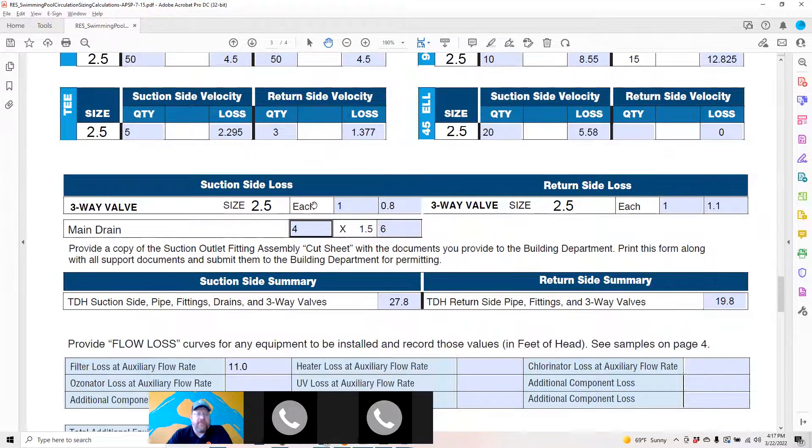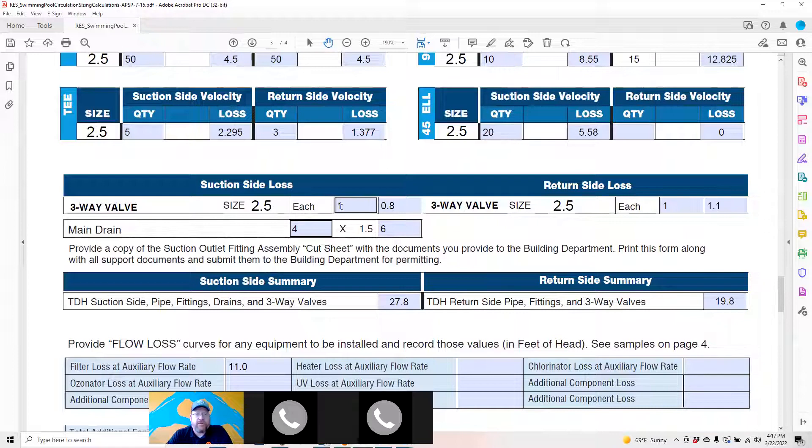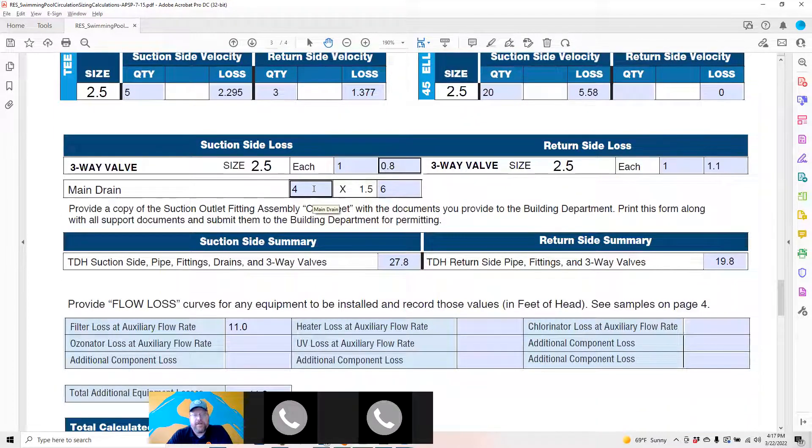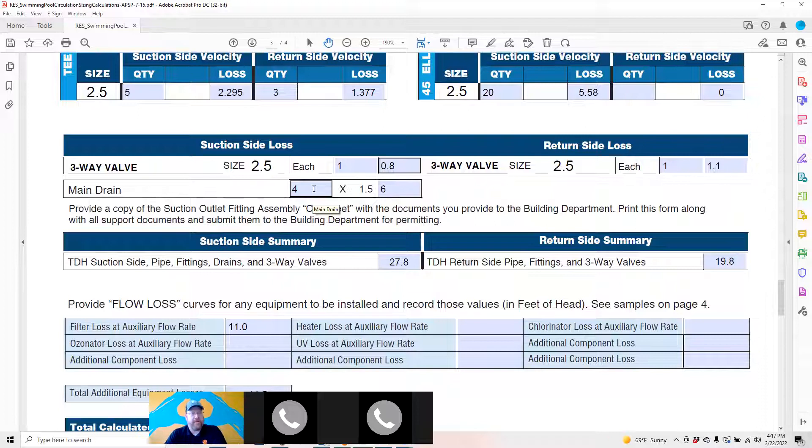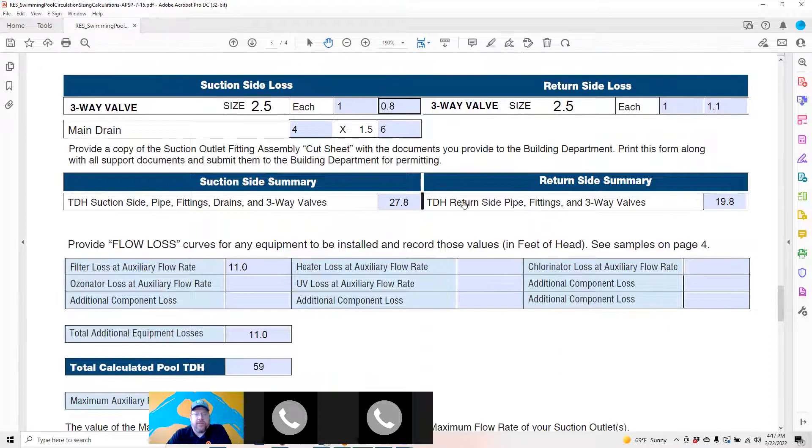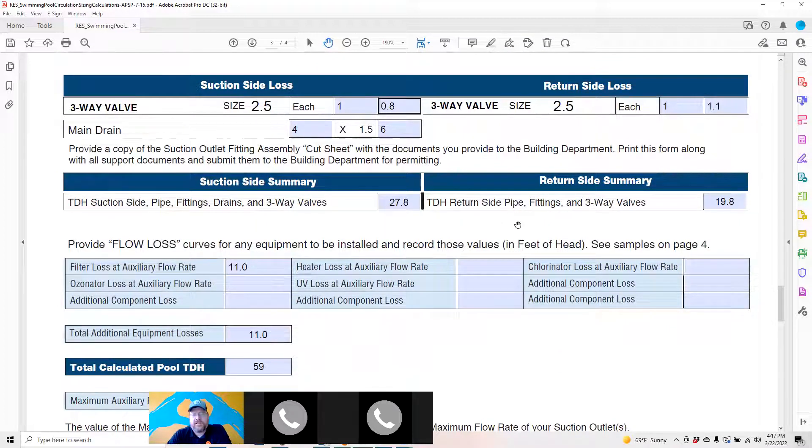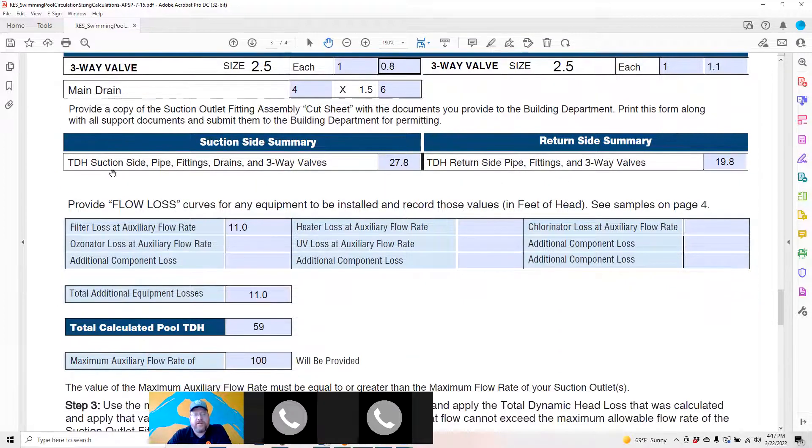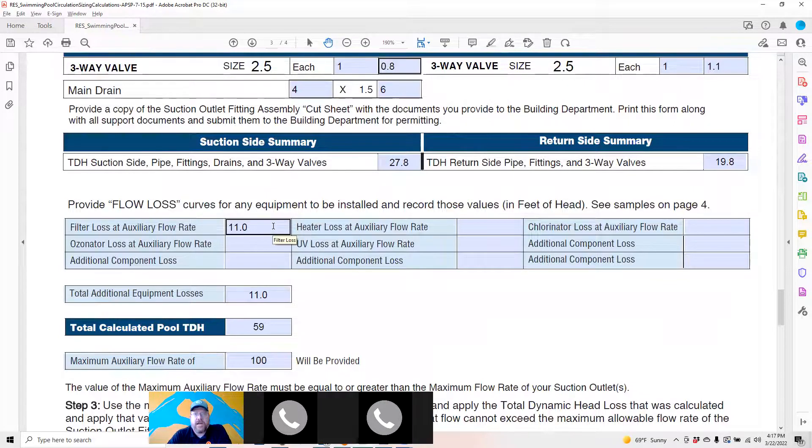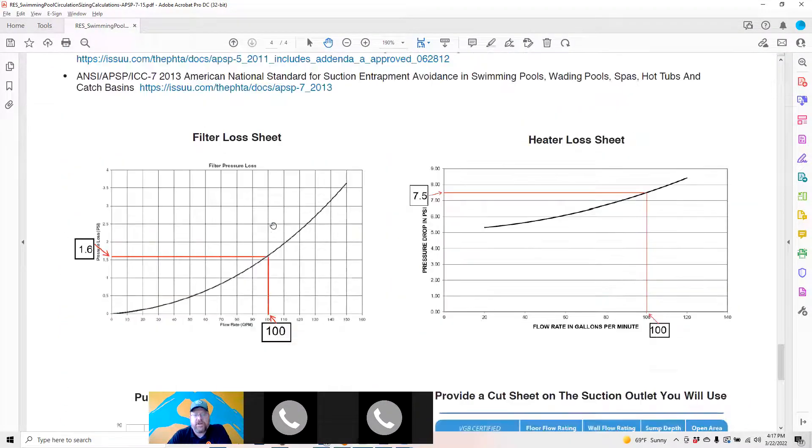Three-way valves here, if you have them for the suction return side main drains. Put how many you got in the pool. Those will calculate the loss of a foot and a half each. From there calculate the total of your suction side and return side, add in the filter loss. Every filter has a curve.